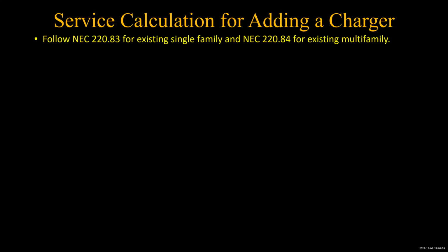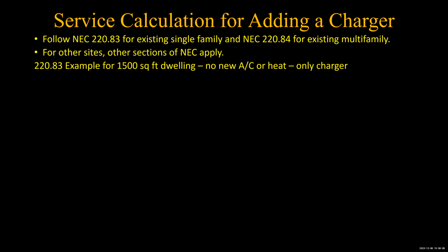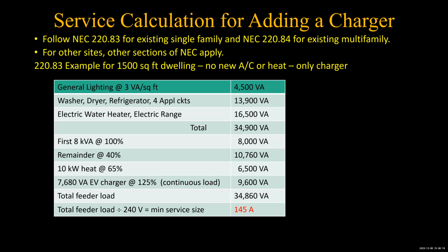Let's say you just have a single family house. If we use this example of 220.83 load calculations, a 1,500 square foot dwelling with no new air conditioning or heat, just a new charger, it's going to look something like this. You've got your general lighting, 3 volt-amps per square foot, 1,500 square feet, 4,500. If you add up your washer, your dryer, refrigerator, and 4 appliance circuits, that gives you another 13,900 volt-amps.